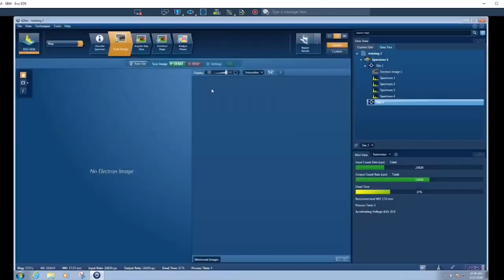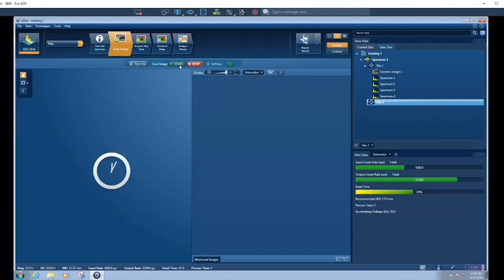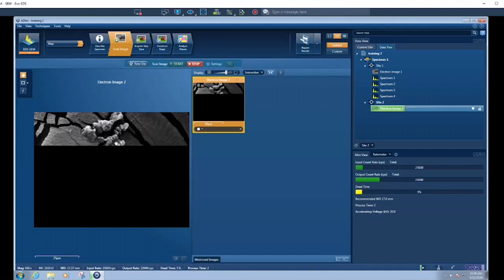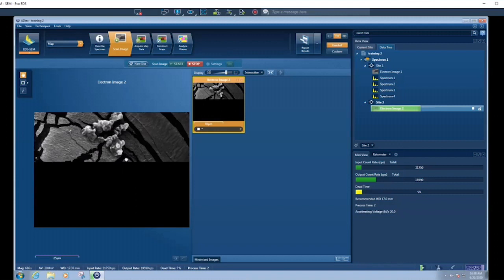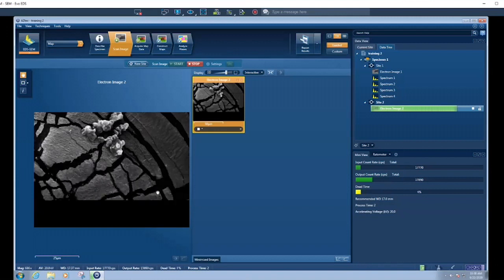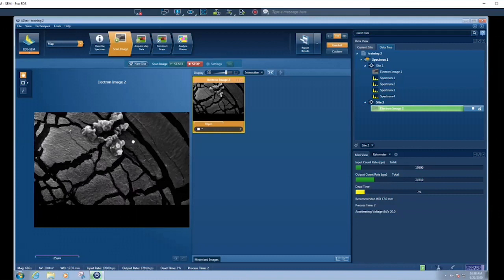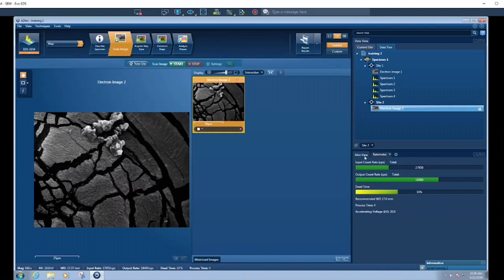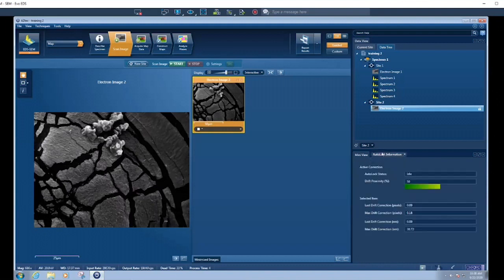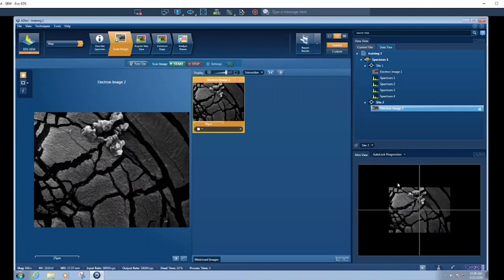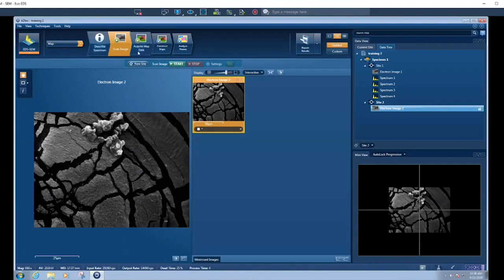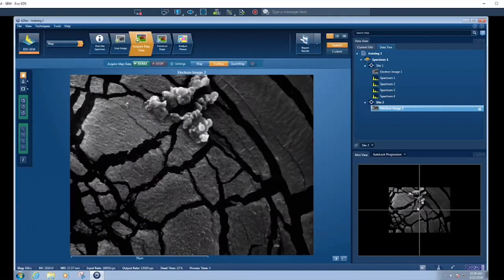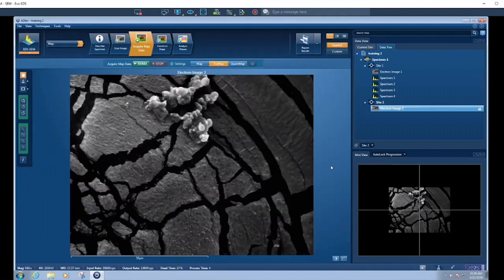Let's go there and start. You'll see it collect the large resolution image, and then it will pause part way through where it will take the small reference image. Here it's pausing, collecting a small reference image. We don't actually see that reference image here, but I will show you where we can see the reference image. If we change down here in this mini view, we can change it to auto lock information. This is where we see how much it's progressing. This is our reference image, our auto lock reference image. I don't think that it will move much at this resolution, but we'll see.